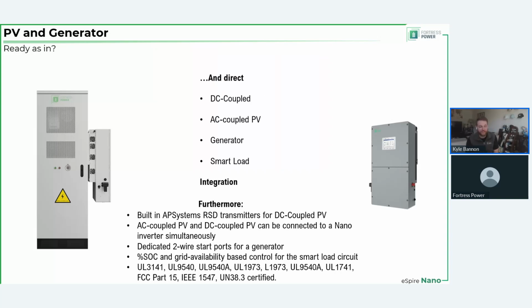Some cool things about the inverter: it can take DC coupled solar, AC coupled solar, it has a generator port, and it also has a load shaving port. So if you're using this for main panel demand mitigation, you hook it up to the main panel with an AC conductor. But say you have an air conditioning circuit or a high power load like an elevator that you don't want to cover when the grid goes down—if you plug that into the smart port of the hybrid inverter, we can shed that load during an outage and remove a ton of unneeded demand in certain situations, all controlled by the inverter's software.